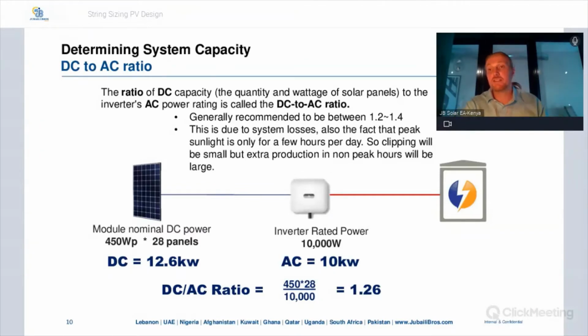So when you have a DC to AC ratio that is above 1, so if it's 1.3, that means all of the off-peak hours will give you additional production. So the mornings before peak sunlight and the afternoons after peak sunlight, you will get more production. On your load profile, we call it the shoulders. Your solar production will be expanded sideways. If you go above 1.4, it's usually not economically feasible anymore. It doesn't give you a good return on your investment above 1.4. So 1.3 is a good DC to AC ratio.